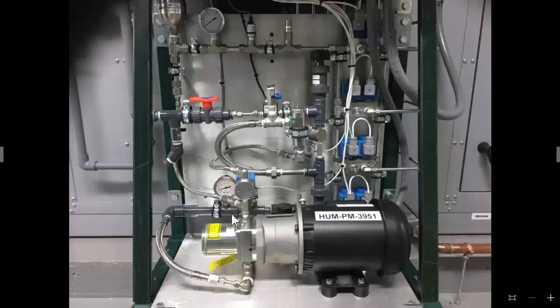So what I'm saying is, at a particular RPM, you can go out into the piping and grab it, and it might be vibrating quite a bit. And at another frequency, it might not feel like it's vibrating so much. And then you can go to a different job where there is a different installation and start feeling in different places, and you might not be able to feel any vibration whatsoever. You can feel the pulsation and maybe not so much vibration, so each job is a little bit different. Overall, these pulsation dampeners do help, and I recommend that they go on the job.